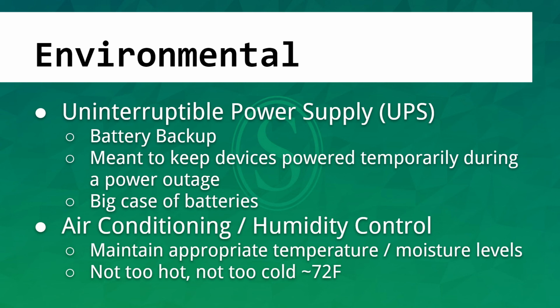You'd be lucky to get 20 minutes out of a series of UPSs in a data center. In our data center, we have two generators outside, and the only point of the UPS is to keep the data center alive so the generators can start up, reach maximum spinning speed, and begin generating enough power consistently—then we can switch over to get power from the generators instead of the power grid. The only purpose of the UPS is that temporary float between losing grid power and getting generator power.